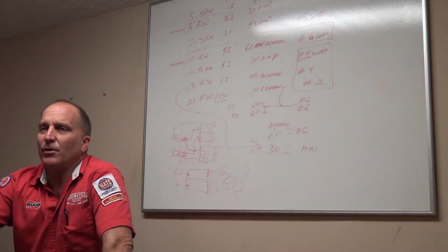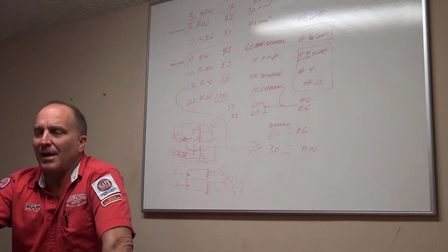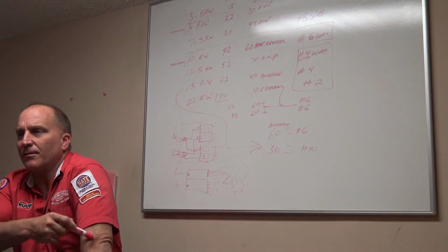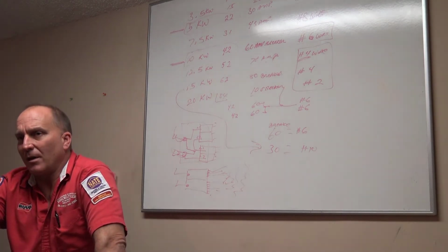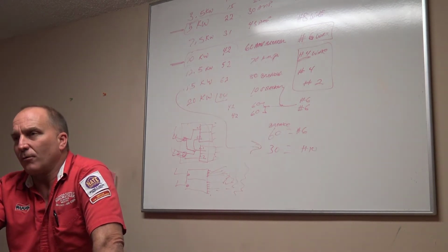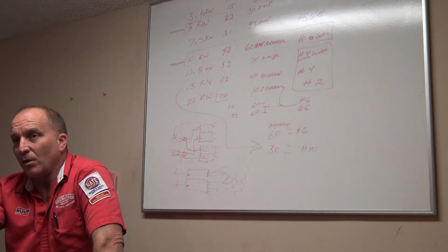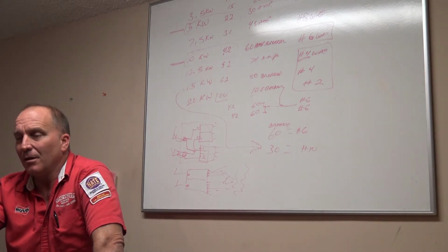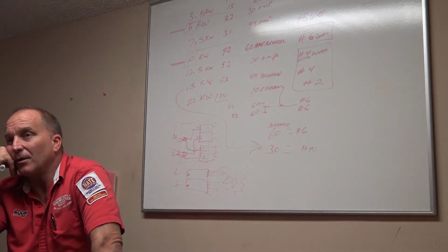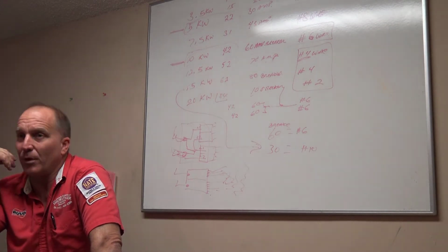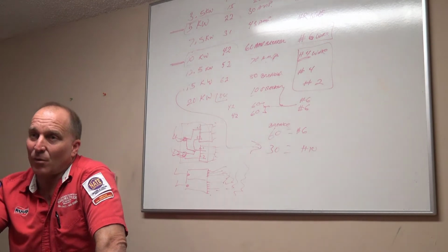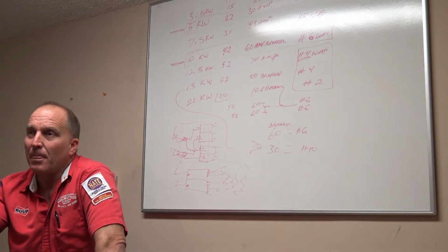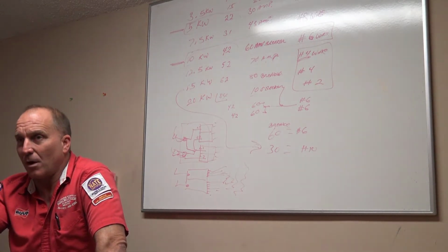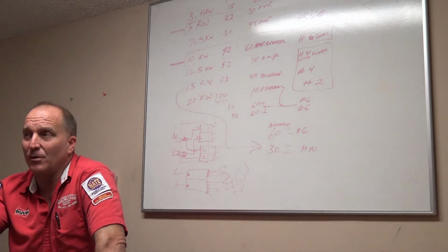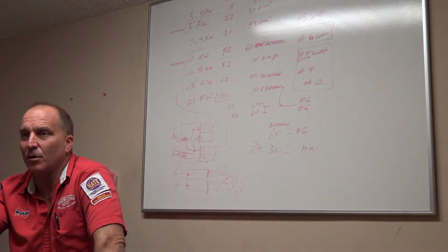The first thing that you have to do when you walk into that customer's house, besides greeting them and presenting yourself and all that kind of stuff, is you turn the heater on. And when you turn that heater on, I want you to take the door off to where you can see the heating elements in there. But before you turn the heater on, the first thing I want you to do is look at the wires. Make sure you don't have any burnt wires before you even turn the heater on. Okay? Before you put power to this system and start running that heating system, you literally need to pull the cover off where the heating elements are, and pull your where your breakers are, or your fuses and all that kind of stuff, and just look at your wires and make sure you don't have burnt wires before you're fixing to apply all this load to it.